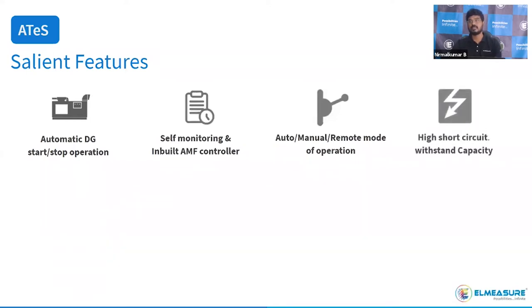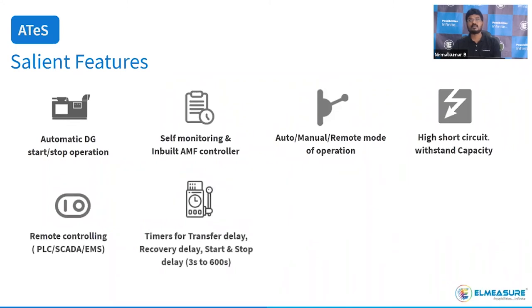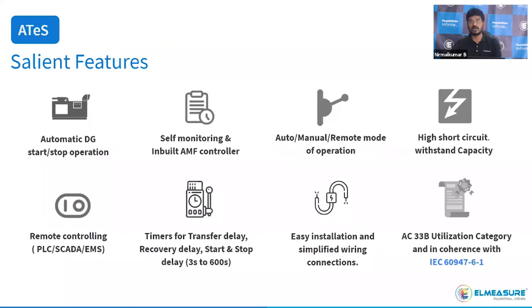High short-circuit withstand capacity: for each rating, it is rated current times 10. So a 125A ATS has a 12.5kA withstand capacity. Remote controlling via PLC, SCADA, and EMS integration facilities are available. All timers are inbuilt — transfer delay, recovery delay, generator start and stop delay — with no need for external on-delay timers. Installation is very easy with simplified wiring and no need for any control wiring or external controller.